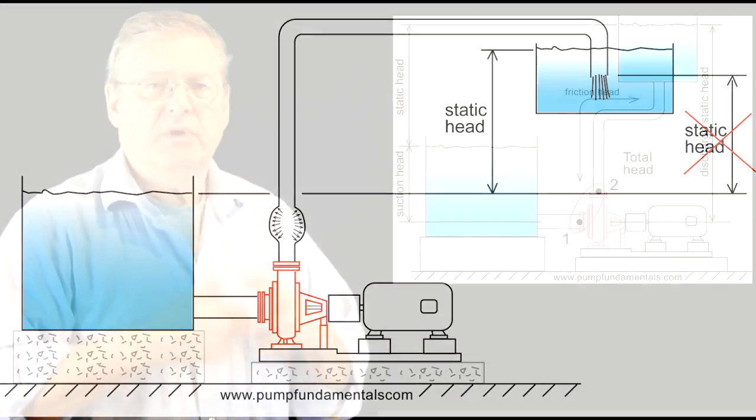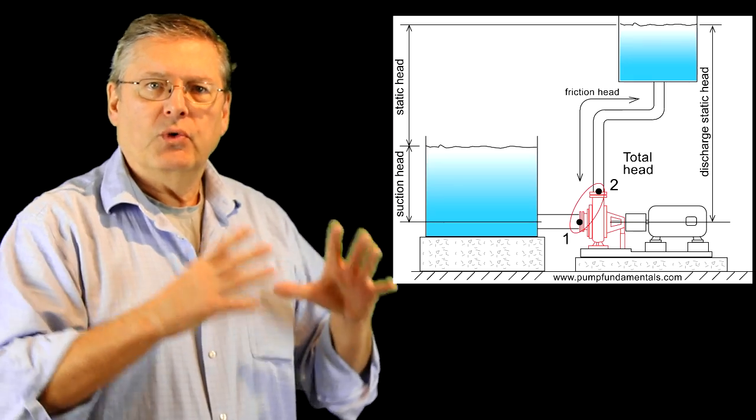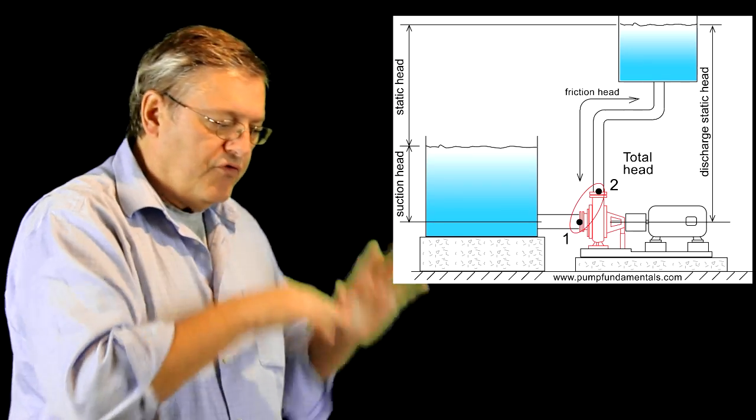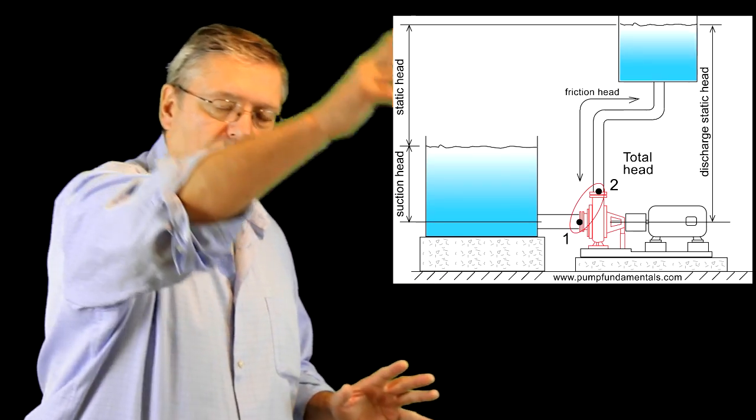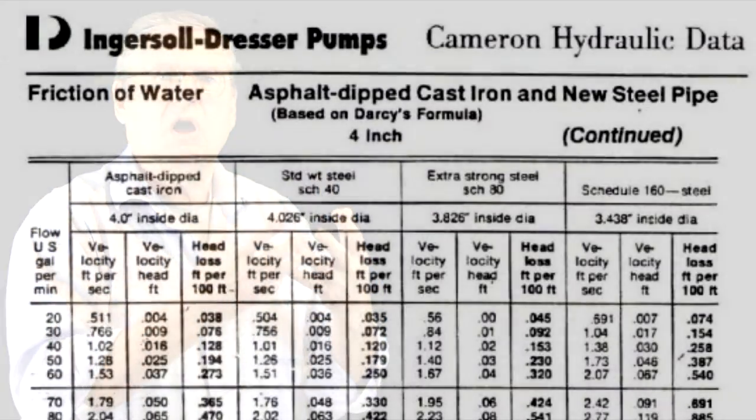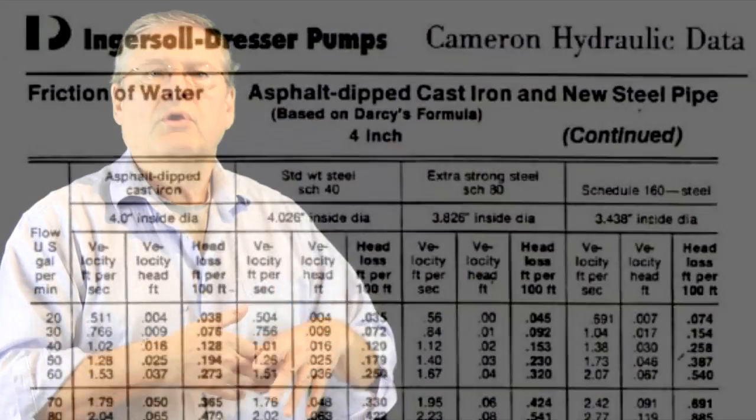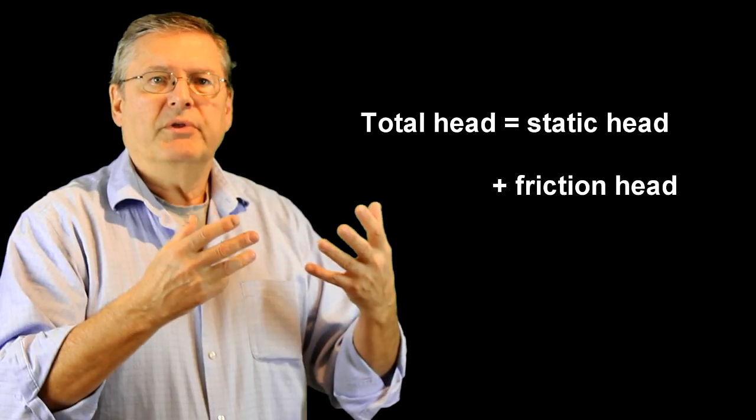One very important term is total head. Total head will be the sum of the total static head, so how far you have to pump from down below to up, and friction head. Friction head is the amount of friction loss there is for a fluid going through a pipe, so it will depend on the velocity, the pipe size, the type of fluid, if it's viscous or not. You can find the value of friction head based on those factors in various ways. There are tables and formulas to calculate it.